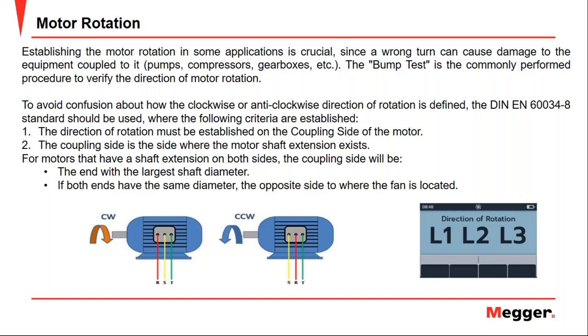The motor rotation is very important because it ensures the proper functioning of the load. This aspect goes hand in hand with identifying the phase sequence of the power supply. Both must match depending on the direction of the rotation required by the load. How do we define the direction of rotation? And this is very important.